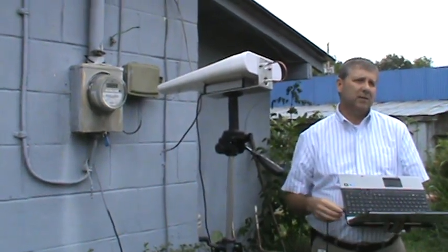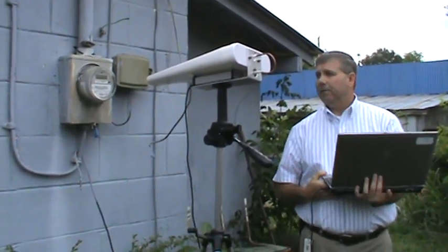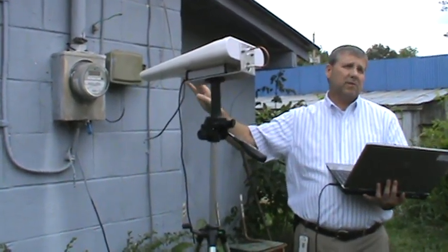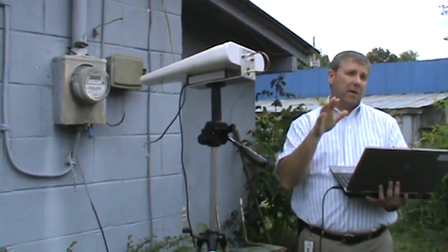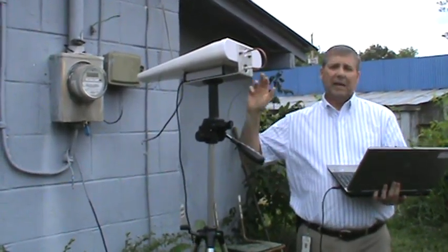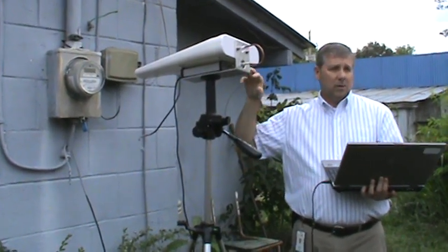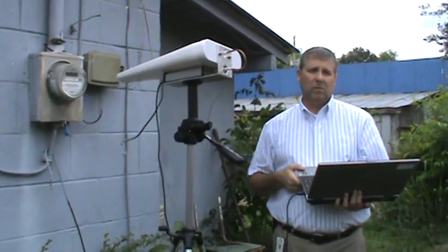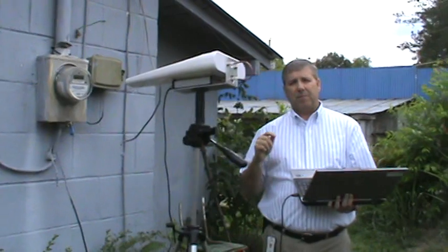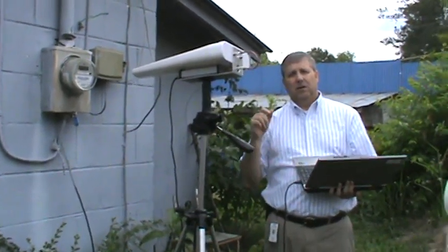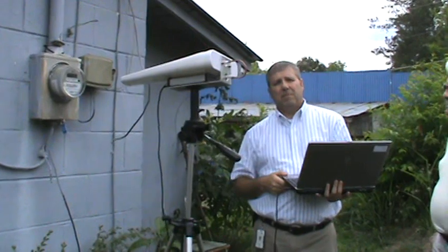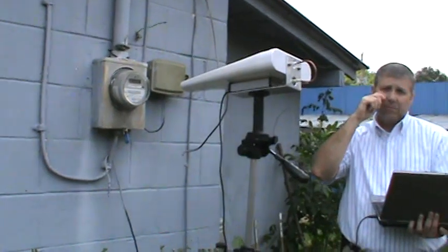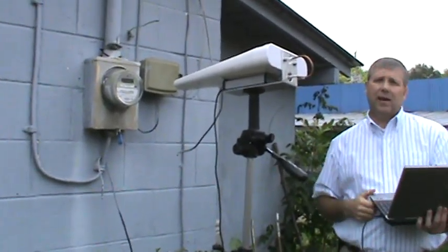All right. And, question. Yes, sir. Who calibrates this? Every meter that comes into our shop, we buy these meters, first of all, they're all FCC certified. There's a certification that Sensus, the manufacturer, has to go through. They ship them to us, and Georgia Power has certified this meter. We put it through all the ANSI testing and certified it. All the meters y'all put out, you do that too? Matter of fact, before a meter can be installed on Southern Company system, it actually goes through our labs and is certified by ANSI. Absolutely. So Southern Company checks this meter? Absolutely. Every meter we put out has been certified.